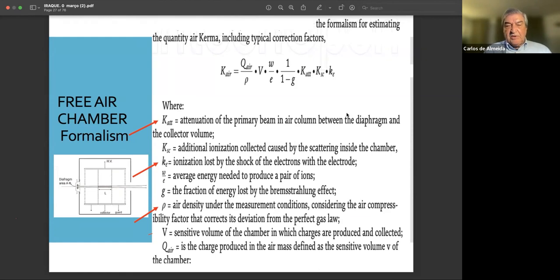In this case, you add a little bit more correction, considering that the air does not follow exactly the perfect gas law, so you have a small air compressibility factor. And then the sensitive volume of the chamber, which changes where charges are produced and collected. This has to be well done, because this is the area where you're going to rely upon, the volume, to define the air kerma for the X-rays. Next one.